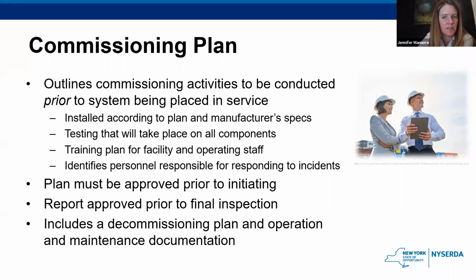Okay, I mentioned this earlier. Another requirement for all system types is a commissioning plan. Obviously, you want to make sure that the system is installed properly and tested prior to turning it on. You want to make sure it's installed according to the manufacturer's specs, test all the components, and make sure there's a training plan for the facility and operating staff that identifies personnel who are responsible for responding to incidents, those folks that we just talked about who can not just relieve the fire department of their duty, but also maybe provide some guidance in the event some folks didn't get training. And that plan needs to be approved prior to initiating or turning the system on. And the report needs to be approved even prior to the final inspection.